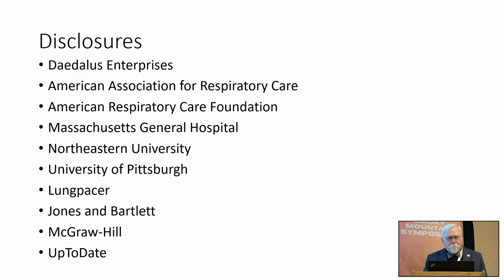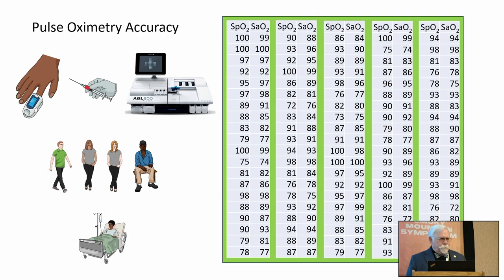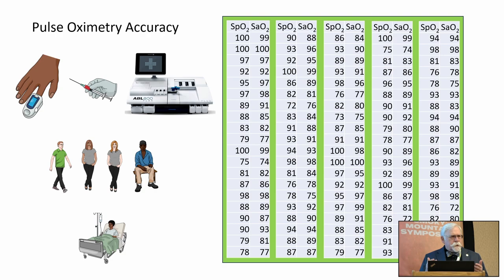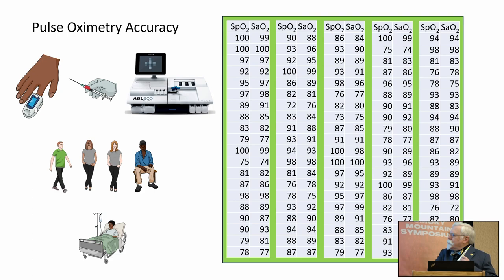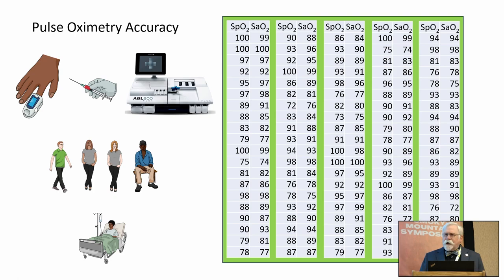Let's talk about the accuracy of pulse oximetry. Consider a study where you evaluate any pulse oximeter: the gold standard reference is an arterial oxygen saturation measured by co-oximetry in the blood gas laboratory. You gather a number of individuals - normal or hospitalized - and compare 100 pulse oximeter saturations to the saturation from a co-oximeter.